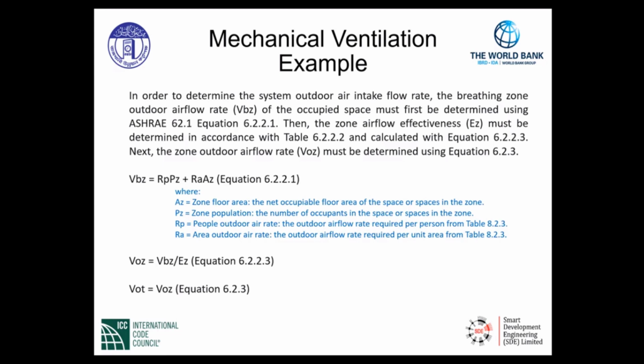rate. V sub OT is our last equation. This is where we will calculate the total amount of air required. And in this case, it's pretty simple. For a single zone system, V sub OT is equivalent to V sub OZ as we calculated in the equation above. Again, this is for a single zone system, equation 6.2.3. Keep in mind, there are other ways to calculate mechanical ventilation for multi-zone systems. ASHRAE 62.1 has other calculation methods for multi-zone systems as well. Our example will focus on only a single zone system.